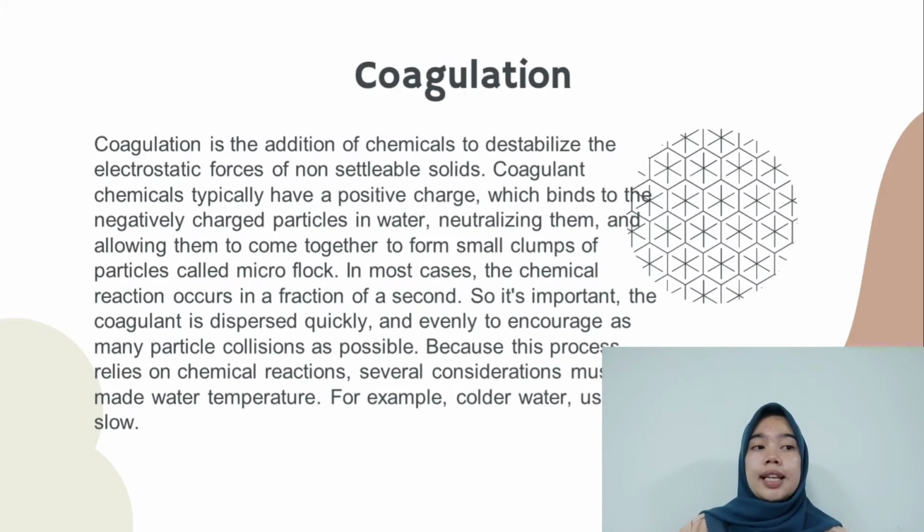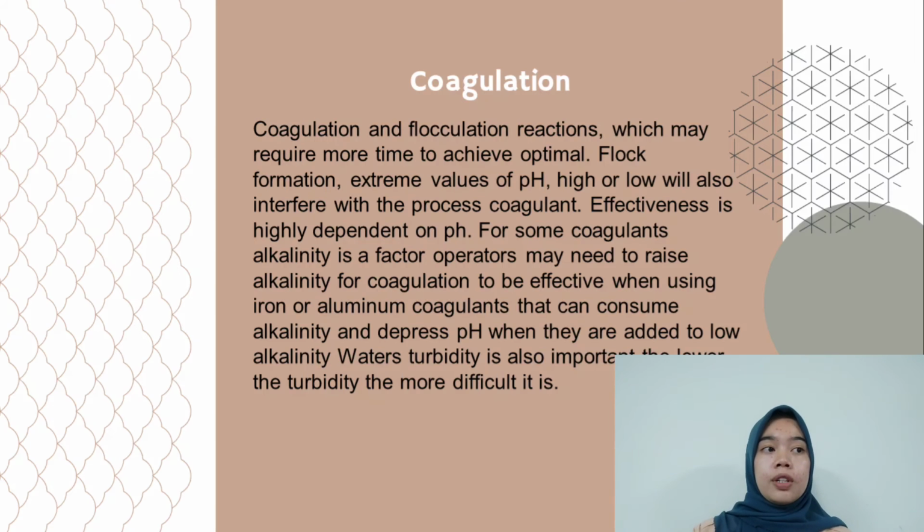Because this process relies on chemical reaction, several considerations must be met. Water temperature, for example: colder water usually slows coagulant and flocculant reactions, which may require more time for optimal floc formation. Extreme values of pH, high or low, will also interfere with the process.